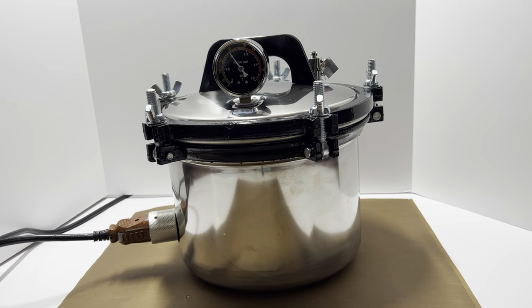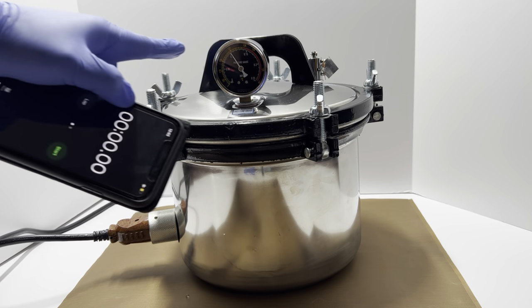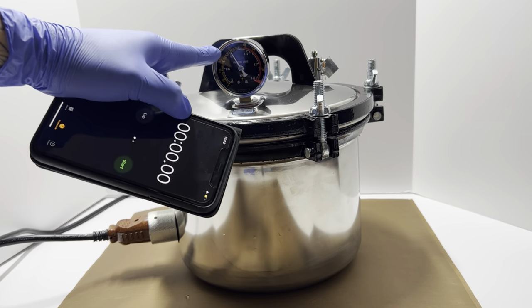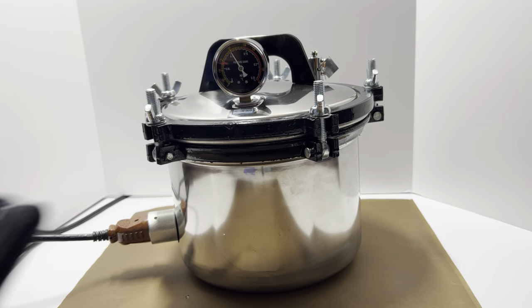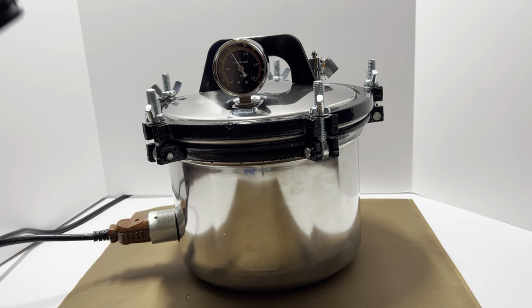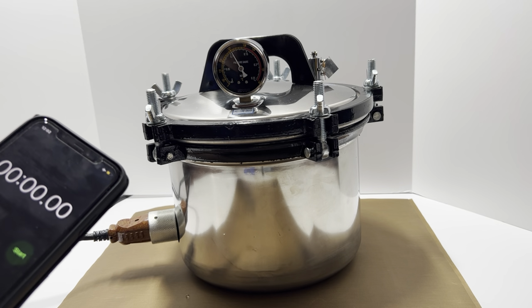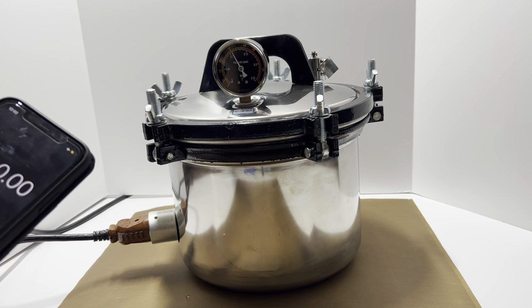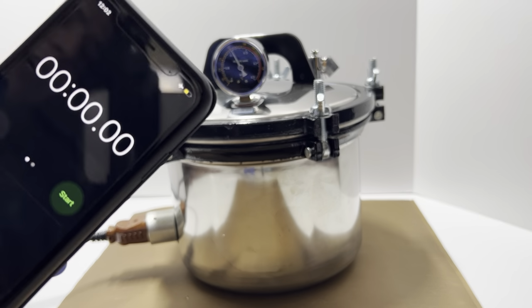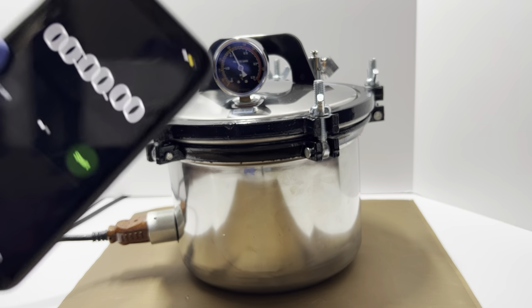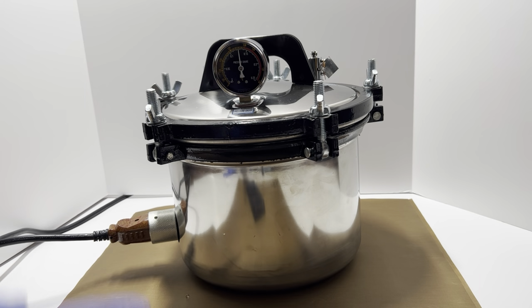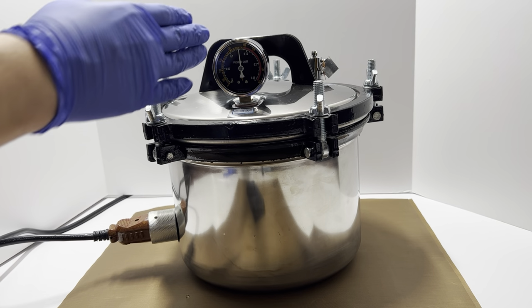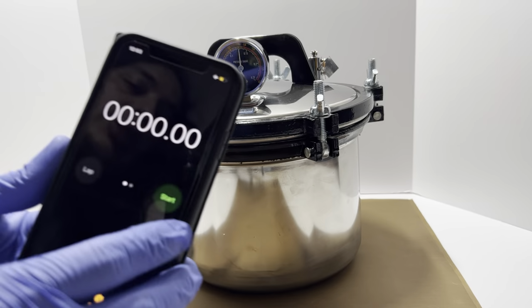So we are now coming up to the temperatures and pressures where I could begin to start the timer here for the sterilization process. As you see, the gauge is showing the reading right there. And I think I'm going to hit the timer here shortly in about a minute or so. And then from there, I'm going to leave this on for about 25 to 30 minutes. So that way we can effectively do what we need to do. So we're reaching the desired temperatures and readings right here. I'm now going to hit the timer.